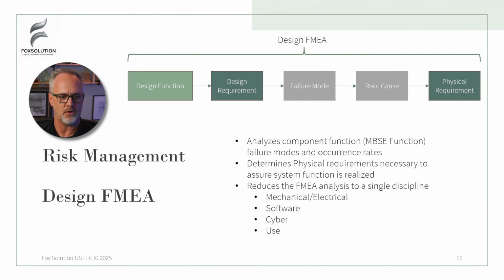It either fails or it passes. There's not this statistical sort of analysis going on. It's 100% or it's 0%. Another example is usability. In usability, we have a construction that is cognition and perception errors. So we perceive something, which causes us to believe something, which leads to actions and use errors. So the format of the FMEAs is different based on the different disciplines. So it's at this level that we start splitting them up into different FMEA formats.